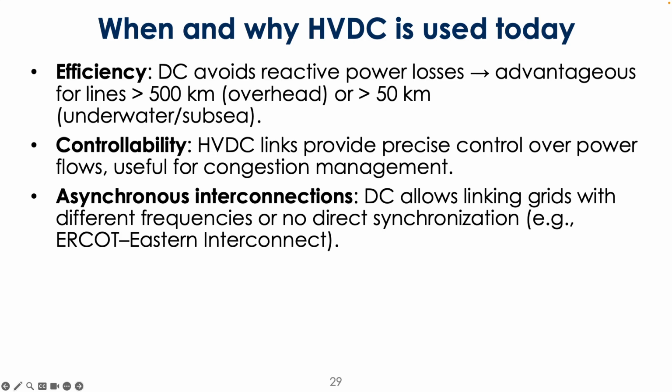Okay, and so when I talk about WECC versus the Eastern Interconnect versus ERCOT, even though we all operate on the same frequencies, those frequencies are technically not in sync. And so you cannot just transmit power from Colorado to Chicago, for example, because you would cross that divide between WEC and the Eastern Interconnect.